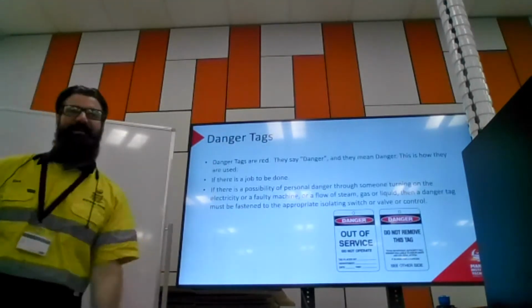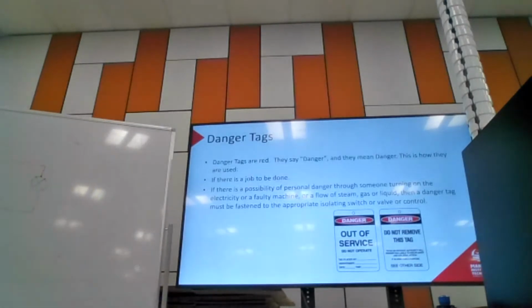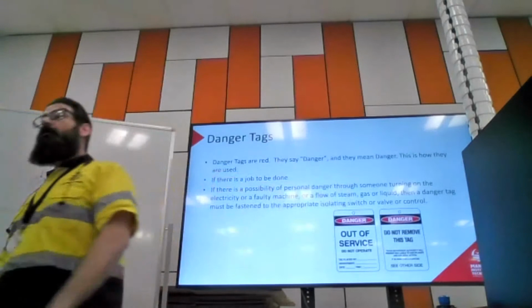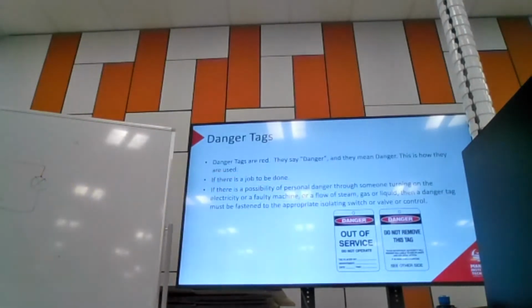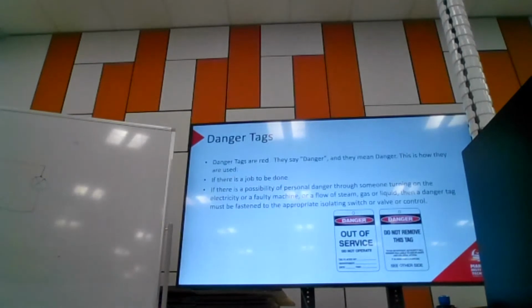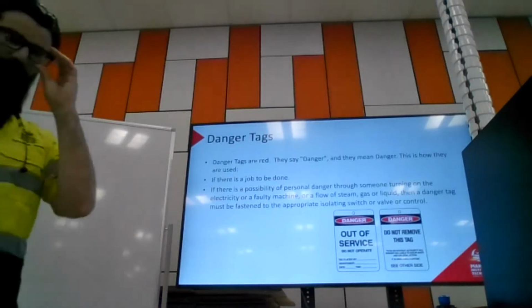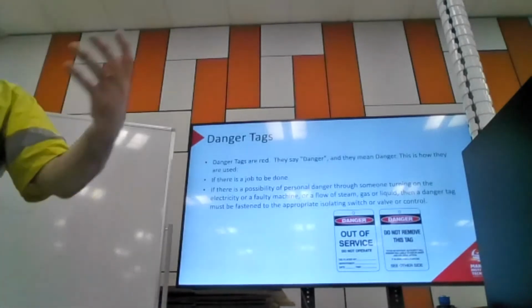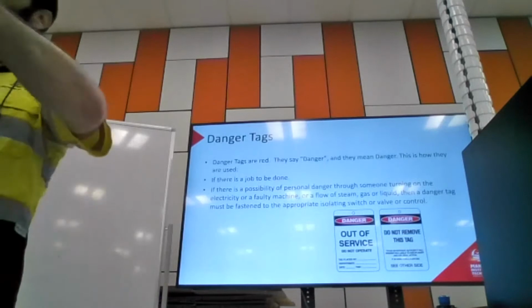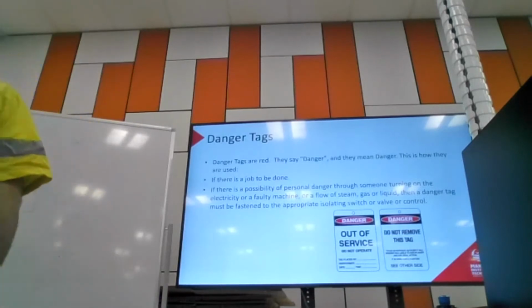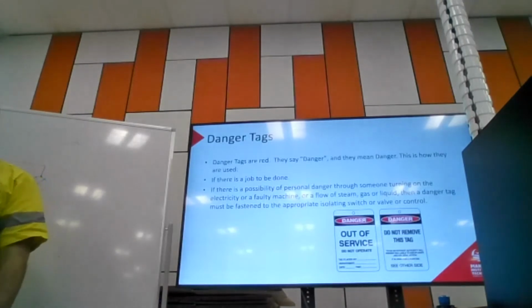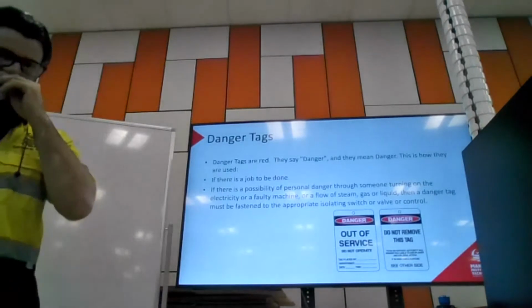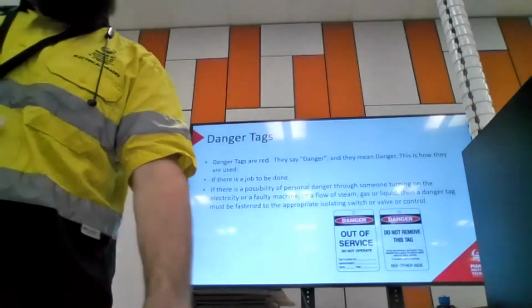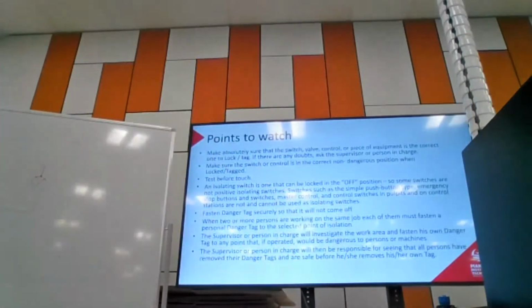So if we have a danger tag on something I'm working on right now, it means if you take this tag off and reliven this circuit, I might die. We may also see danger tags on other pieces of equipment, like isolation valves for liquids or gases, which are often lockable too, and you can lock and tag those for exactly the same reason. In my experience with underground fuel pipes, if I'm doing work on a dispenser and need to disconnect the pipework, I'll turn off the valve going to that pipework, if not the whole pump, and I'd lock and tag that valve as well, because I don't want somebody else turning it back on and giving me a face full of petrol. Apart from being unpleasant, it might set me on fire.